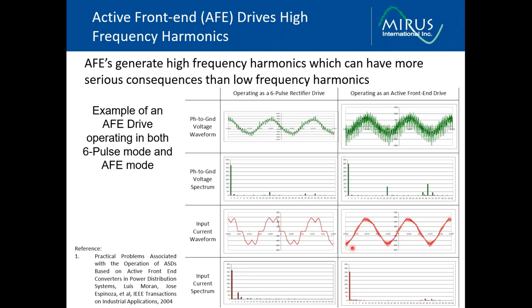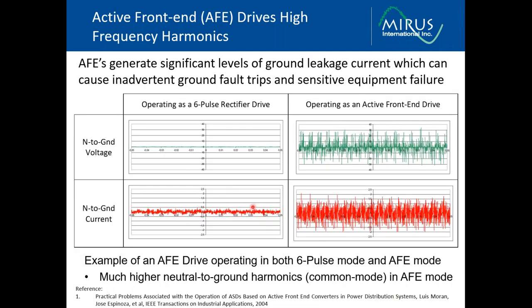But the active front end drive, although it had lower levels of the lower frequency, it definitely had evidence of a high frequency current being drawn at the IGBT switching frequency. They also took measurements of neutral to ground voltage when operating as a six pulse drive, fairly low levels of neutral to ground voltage. That certainly did drive some neutral current, but again, relatively low levels of neutral current. But in the AFE mode, much higher levels of neutral to ground voltage, which drove much higher levels of circulating common mode currents.